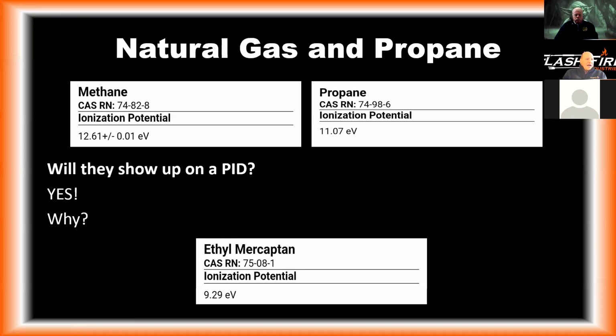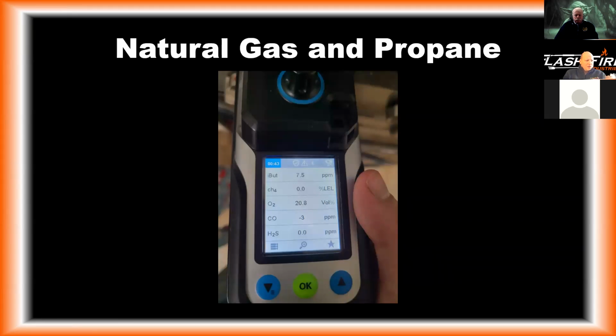And we have to remember that natural gas and propane do not have an odor. An odor is added to them. The odor is usually ethyl mercaptan that's added to them. And if you look down there, the ionization potential of ethyl mercaptan is 9.29. So if you go into a natural gas leak and you're carrying the new meter that I'll go through with you that the safety officer has, you're getting readings on the LEL, but you're also getting readings on the PID. Realize that that's why you may be getting readings on the PID, because of the odorant, the ethyl mercaptan that's put into that gas. And you will probably actually get that reading before you get the LEL.